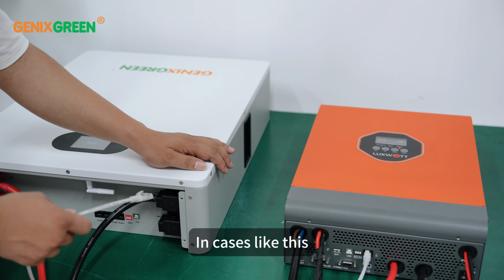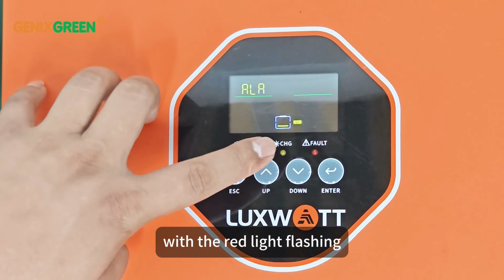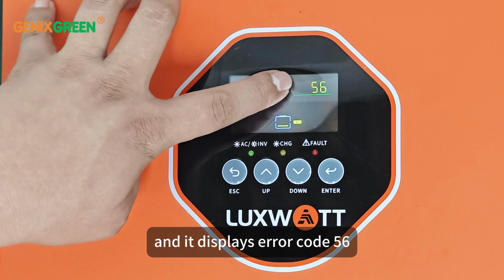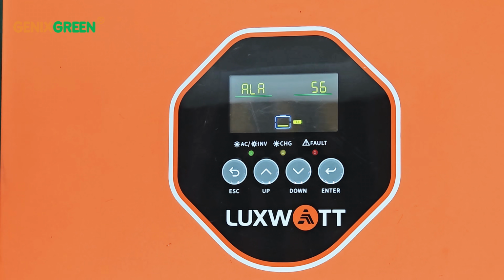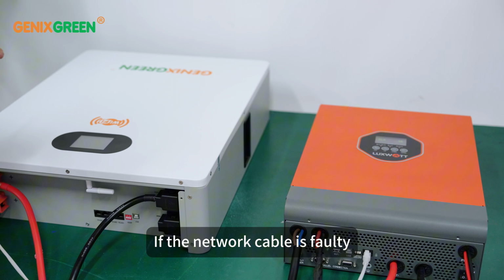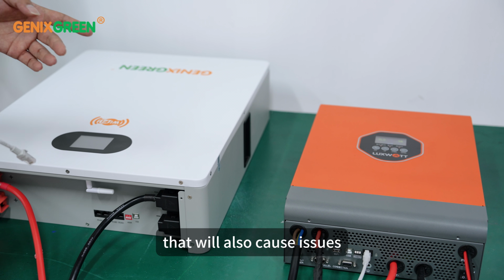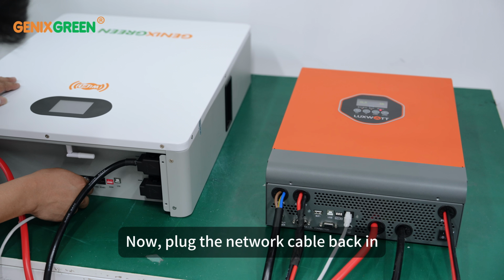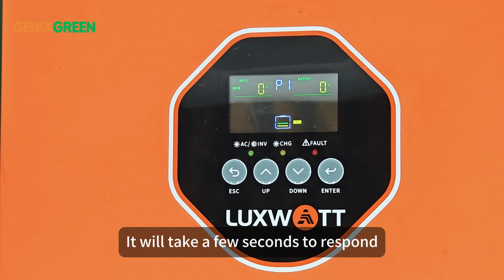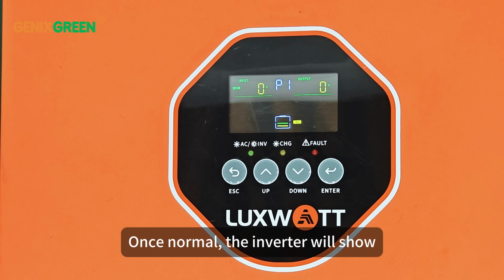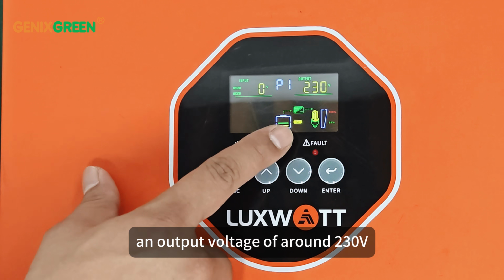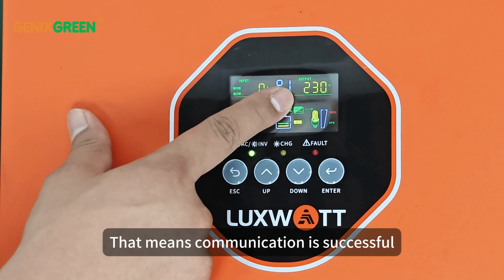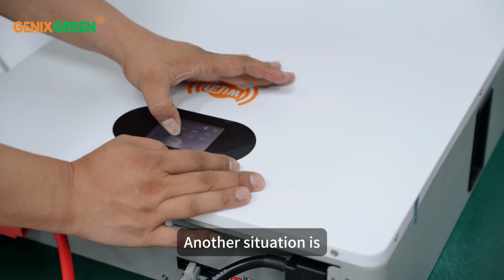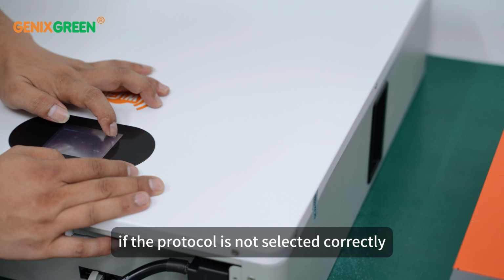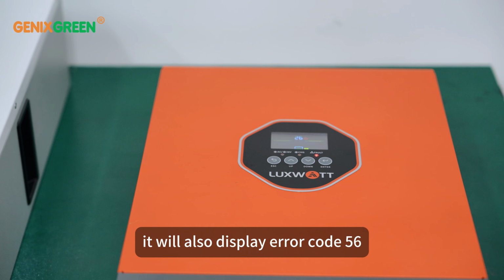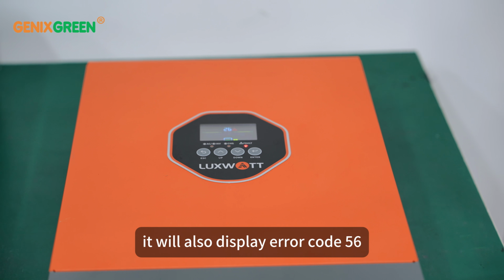In cases like this, if the inverter shows an error, with the red light flashing, and it displays error code 56, that means communication has failed. If the network cable is faulty, that will also cause issues. Now plug the network cable back in. It will take a few seconds to respond. Once normal, the inverter will show an output voltage of around 230 volts. That means communication is successful. Another situation is, if the protocol is not selected correctly, it will also display error code 56.